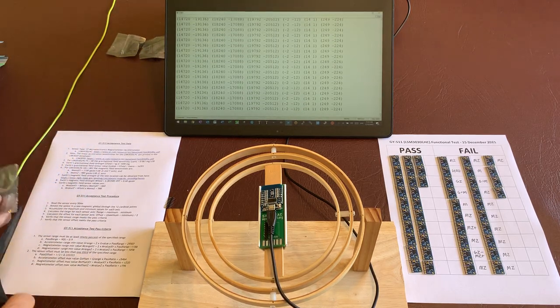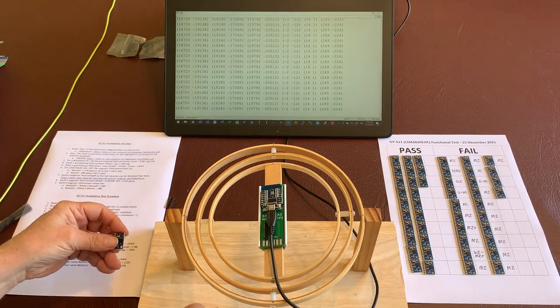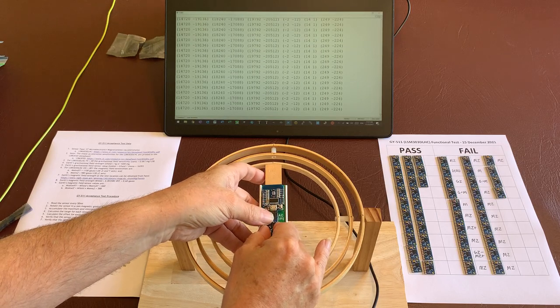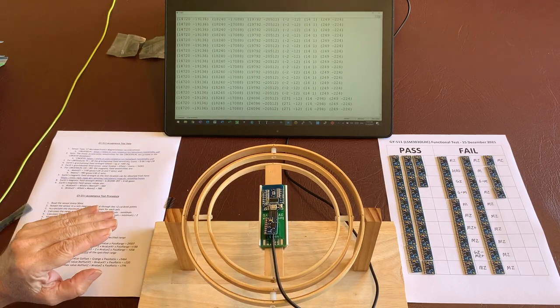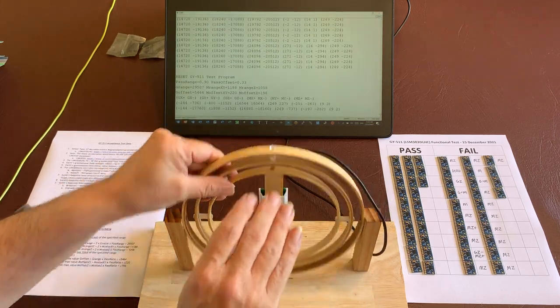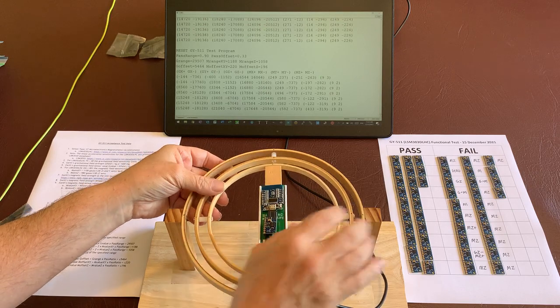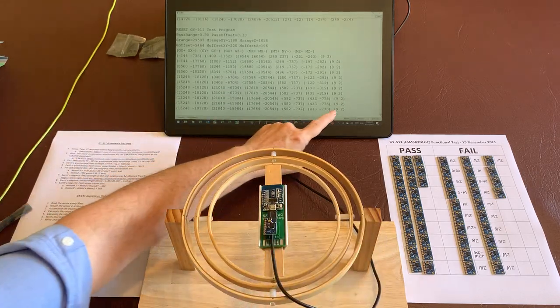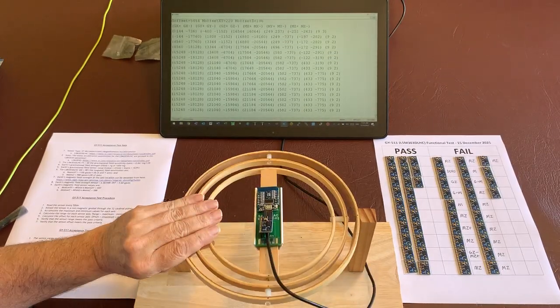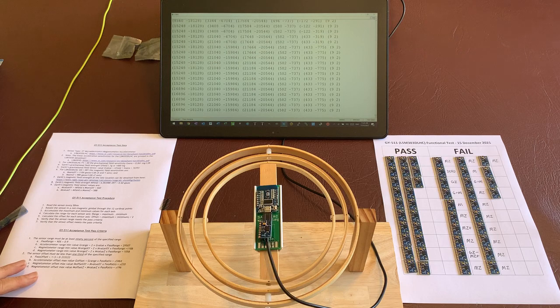The next one. I'll go through the different failure categories in just a moment. Reset. Do our little dance. I can see there the MZ is hardly responding at all. Here's the Z axis — that's not responding at all. Looks like the other axes are okay. So that's an MZ failure. That's probably the most frequent failure we have. Two more to go.